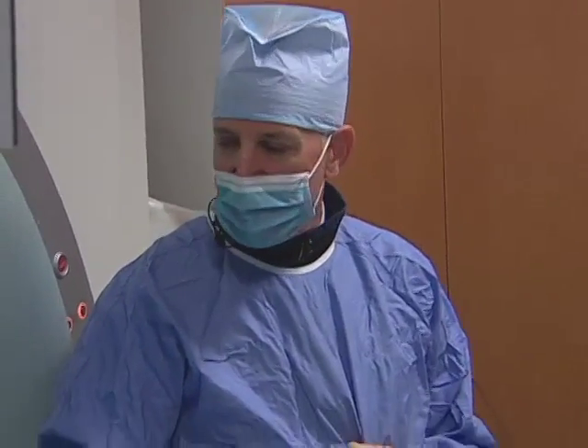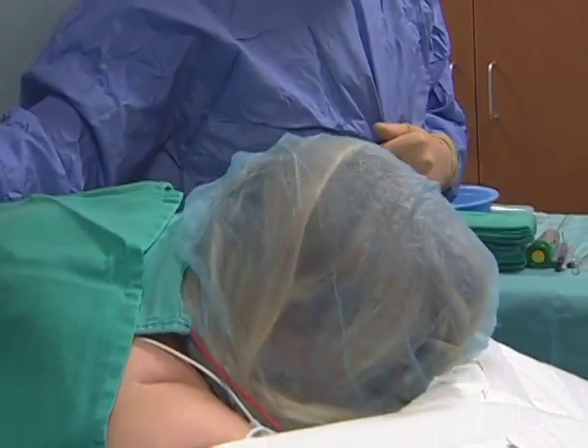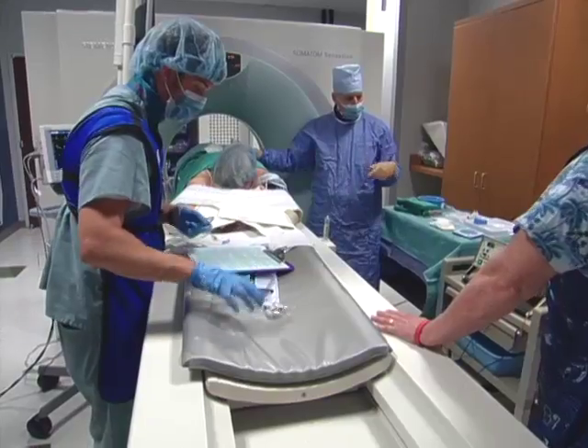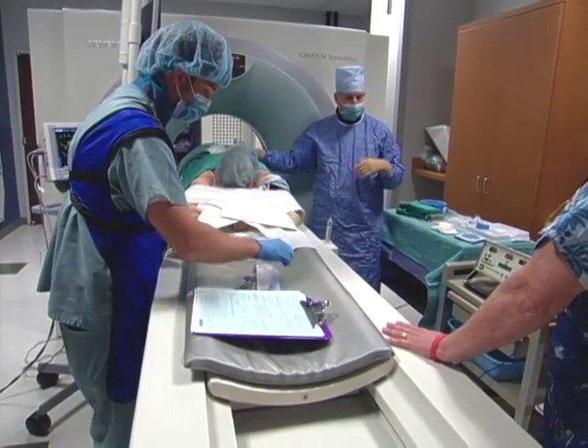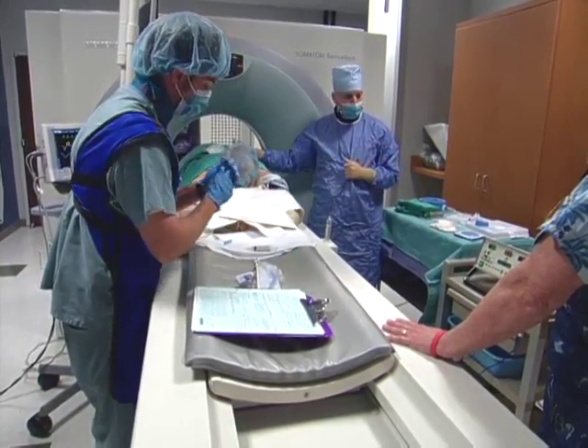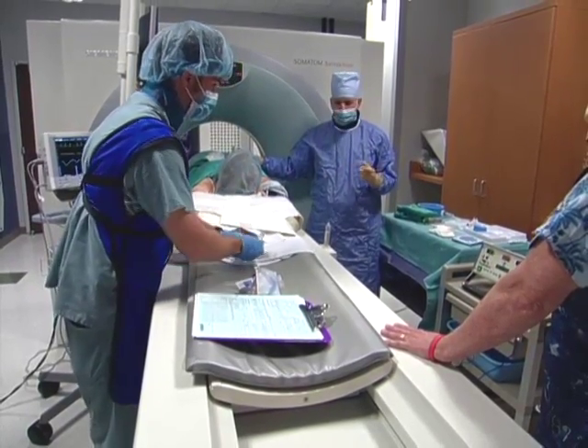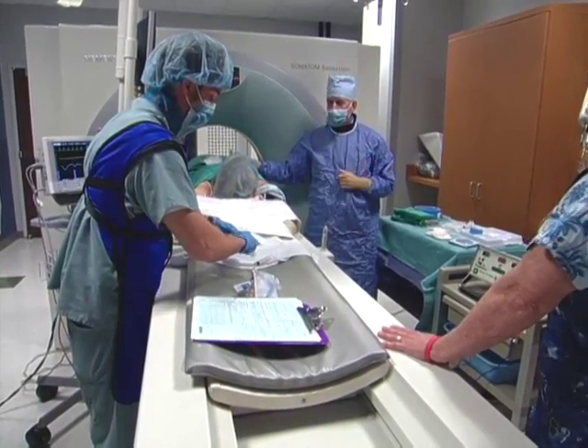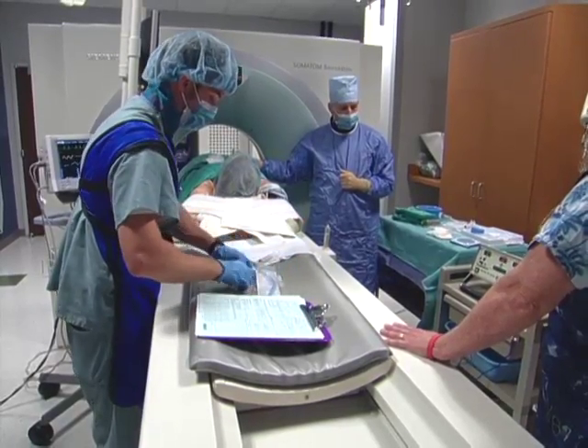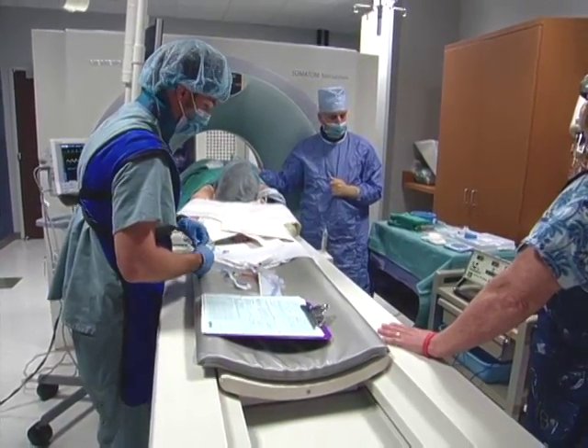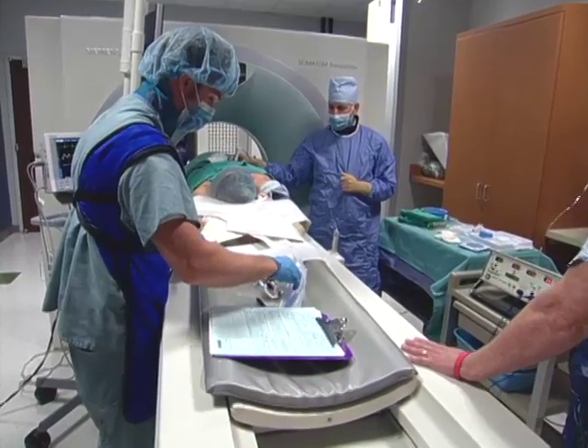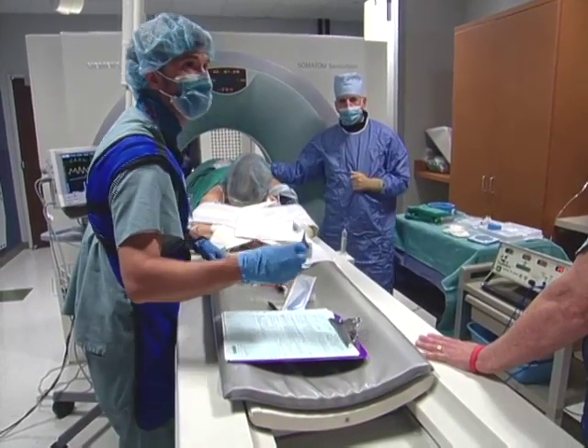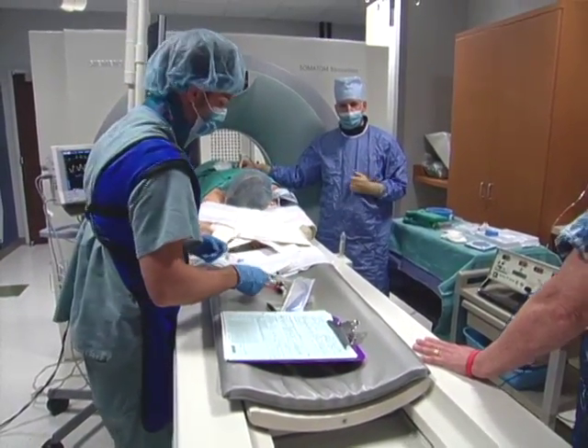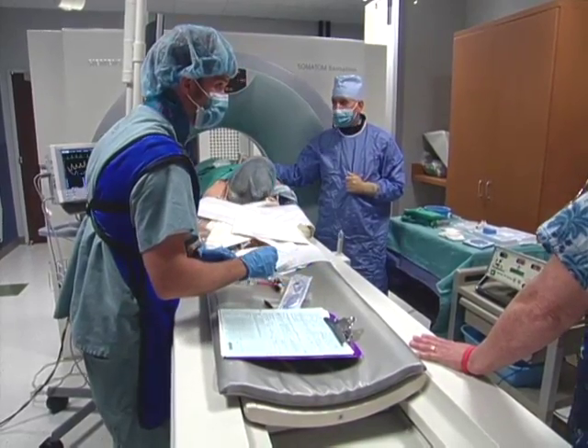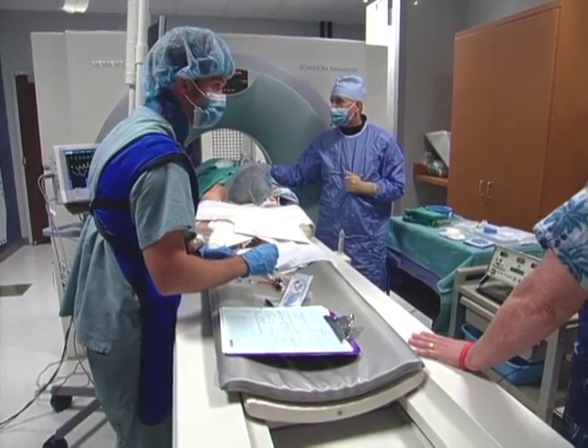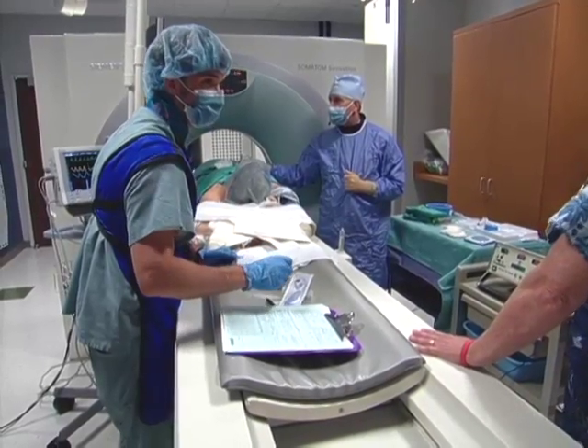Again, the ablations go fairly rapidly, so we're already 2 minutes into this, and this has been rolling off, meaning it's reached those high impedance rises quickly. And during the turn-off phase, there's very little ablation. So once we get repeated impedance roll-offs, then we usually discontinue this after a minimum of about 4 minutes. So we're going to do a 4-minute ablation and then move the probe. With tumors that are larger than a centimeter or so, it's advisable, in my opinion, to do multiple overlapping ablations. So I'll do at least 2 ablations on this 2 centimeter lesion.